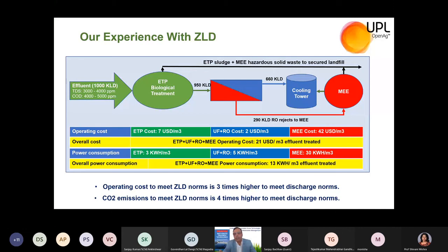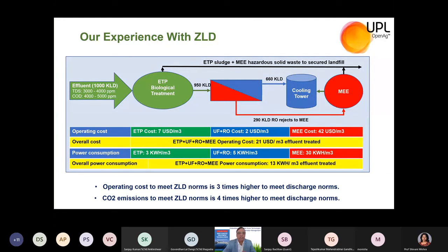The wastewater gets treated and ZLD is achieved. First there is ETP biological treatment, then a reverse osmosis system, and the reject from RO gets treated through MEE. We utilize the permeate RO water in cooling tower, and by this way the industry achieves zero liquid discharge. The operating cost to run conventional biological treatment is nearly $7 USD per cubic meter, and at the tertiary stage — UF and RO — that cost comes around $2 USD per cubic meter.